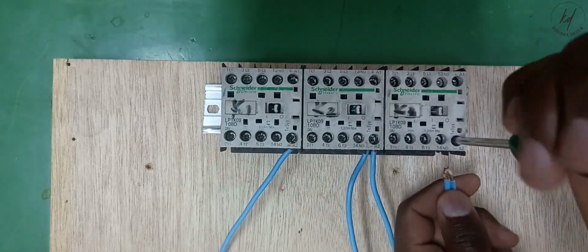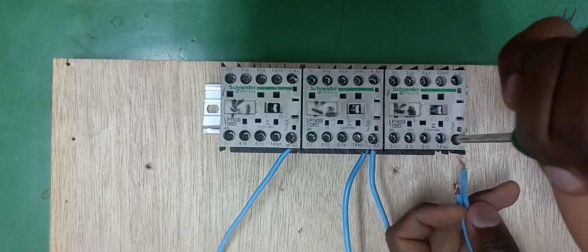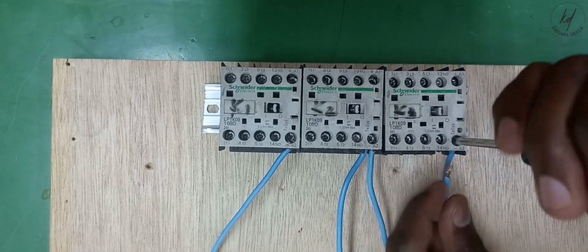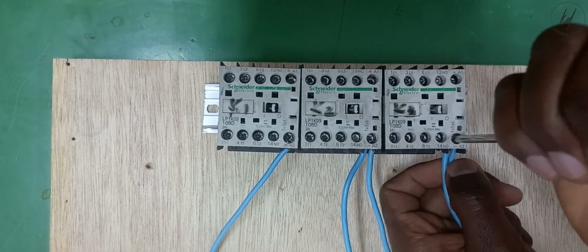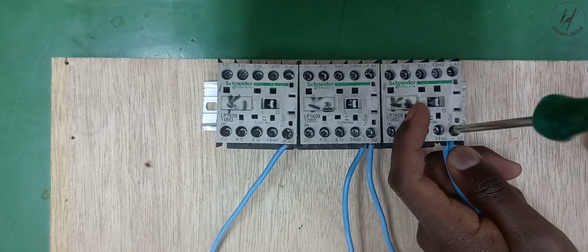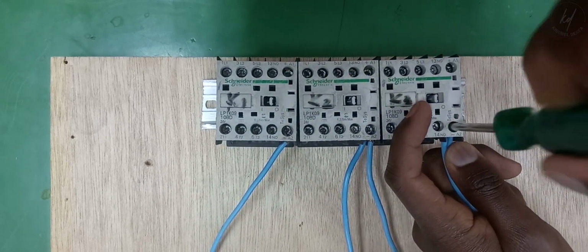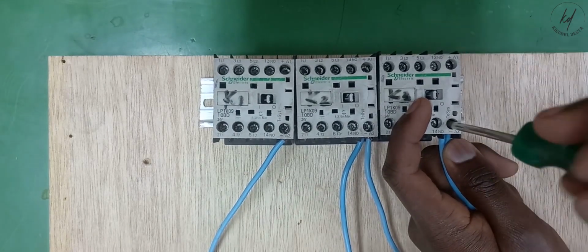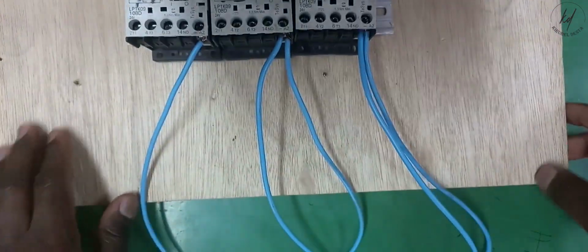6. Torque and current performance of the Star Delta starter is good. 7. It draws 2 times the starting current of the FLA, full load ampere, of the connected motor. 8. It reduces the starting current to approximately 1/3, as compared to a DOL, direct online starter.